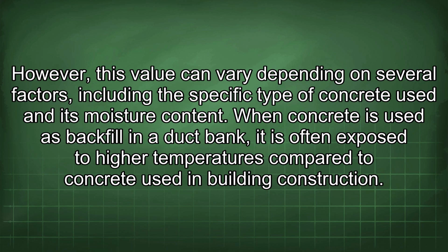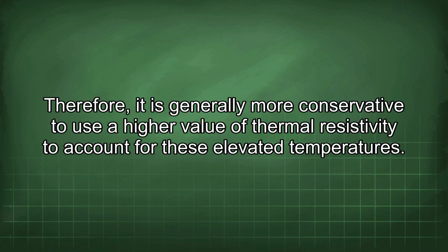its moisture content. When concrete is used as backfill in a duct bank, it is often exposed to higher temperatures compared to concrete used in building construction. Therefore, it is generally more conservative to use a higher value of thermal resistivity to account for these elevated temperatures.